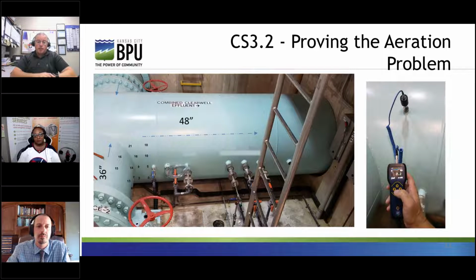Readings were highest midpoint up both pipes, but dissipated downstream from the 36 to 48 inch intersection of the pipe. We finally had proof of concept that it was air. Now only one thing remained: confirmation and solution, as we'll see in the next couple slides.